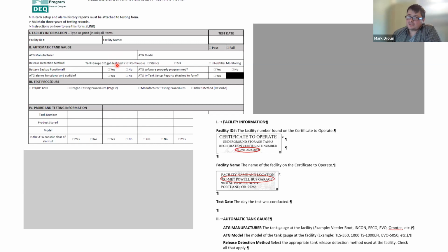You're going to want to test your tank probe. Now, if you're doing SIR, statistical inventory reconciliation, you'll want to test those probes specifically for that. And if you're doing interstitial monitoring, you're going to want to test that sensor, not necessarily the probe. So there's a little variation, and it's going to be critical for you to understand that, to know what needs to be tested. I'll get into that in a second in greater detail.